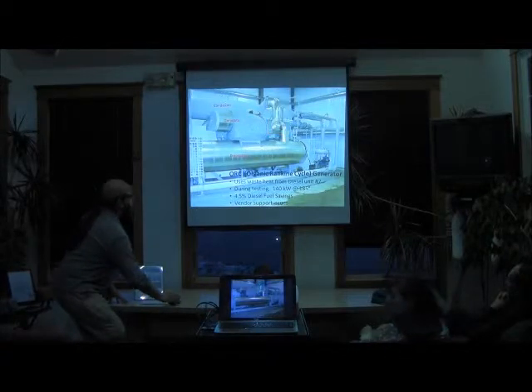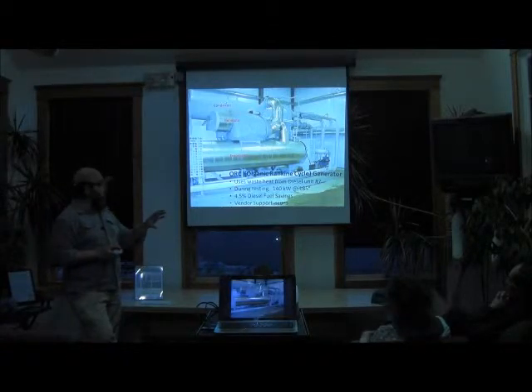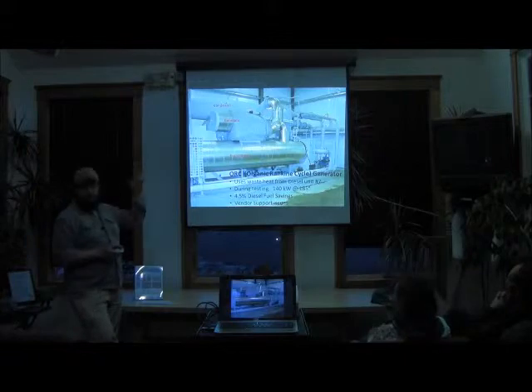So that's the waste heat exchanger, and then your engines also turn generators. Yeah, the diesel engine itself turns a generator. This is just connected to the generator set, and then we're just pulling off that jacket water to get a little more energy out of it.